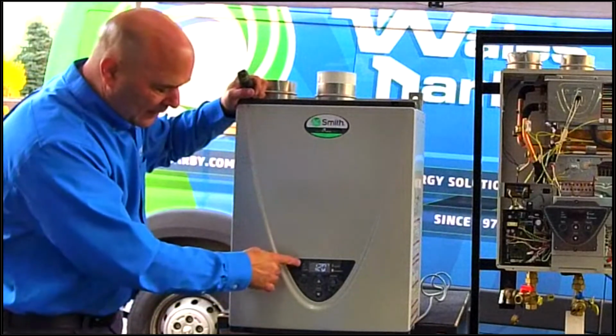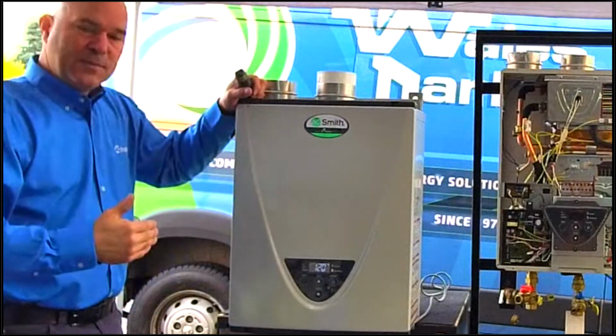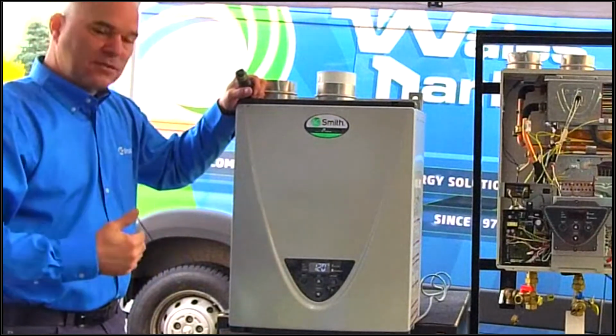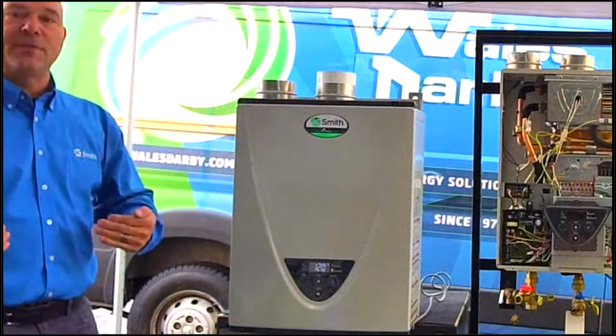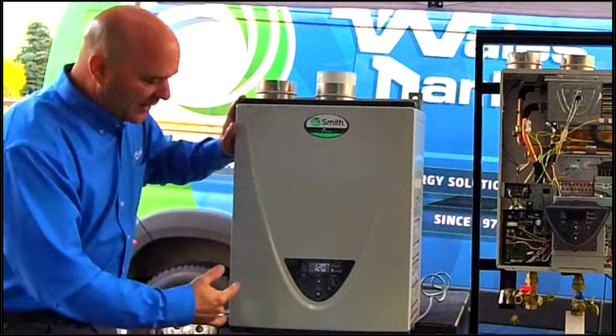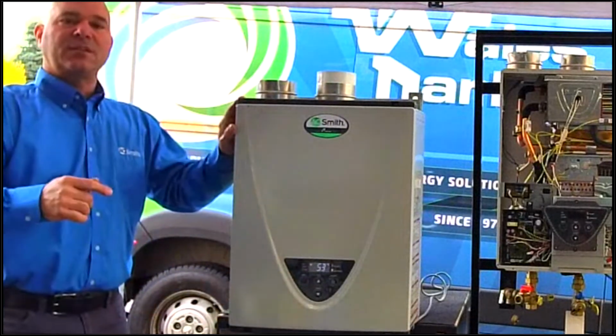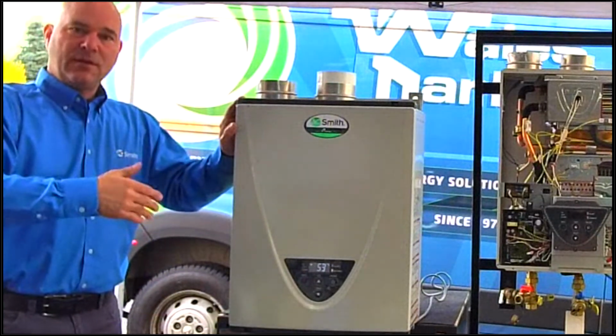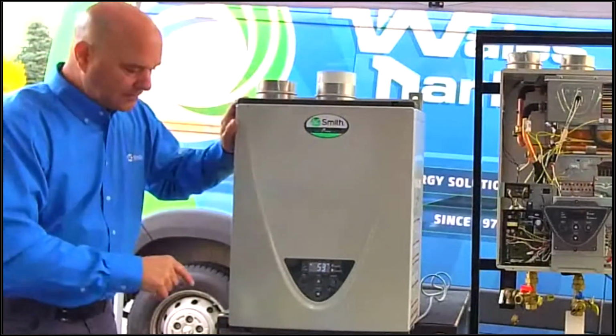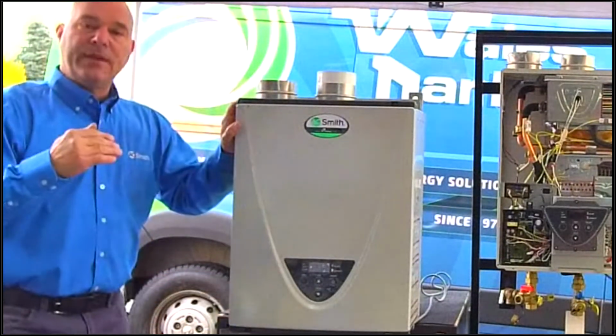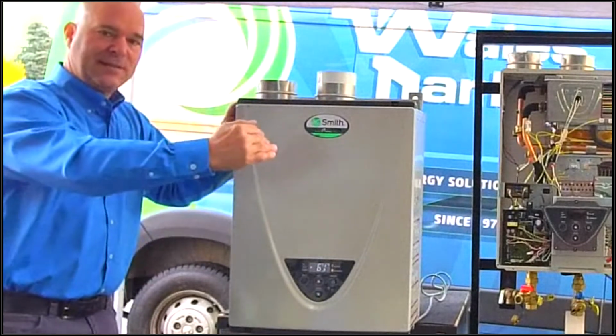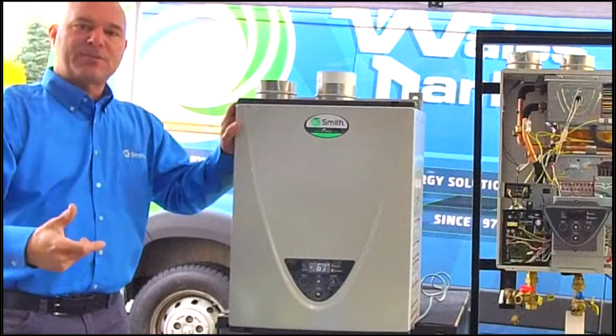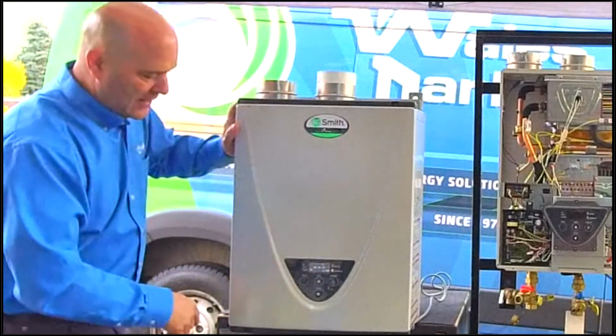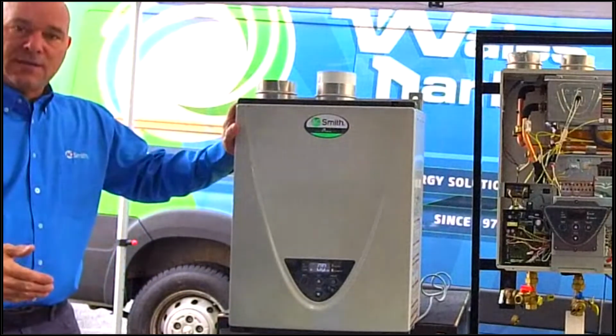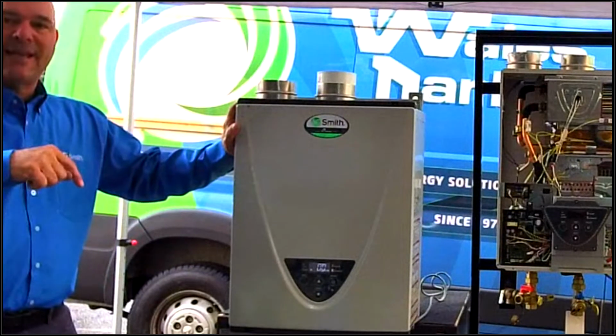If I want to know what the machine is doing, if I want the machine to talk to me, I'm going to go to the information button because I'm looking for information from the unit. If I hit the information button one time, it's going to tell me the inlet water thermistor, the water temperature entering the heater. If I push it again, it's going to give me the water temperature exiting the heater. That would be my target temperature, 120. And if I push it again, it will give me my flow rate based on what's happening at that moment.